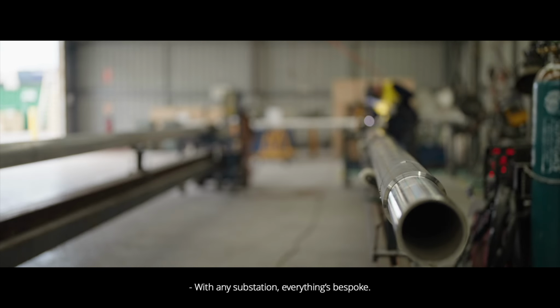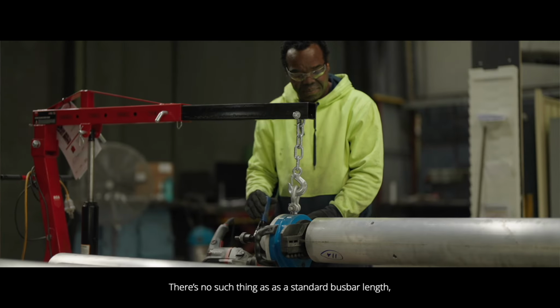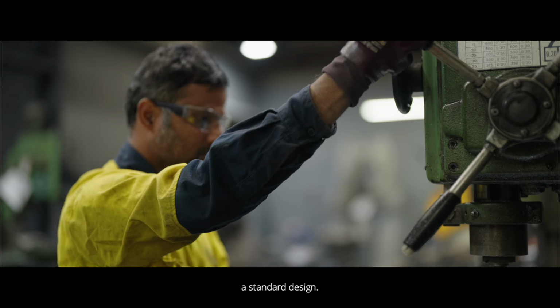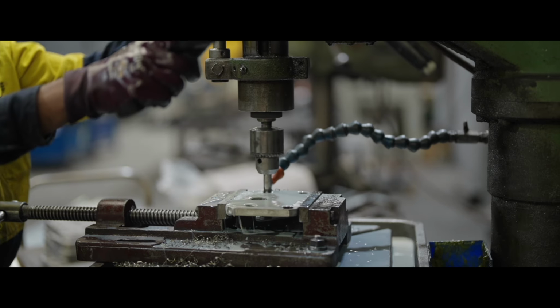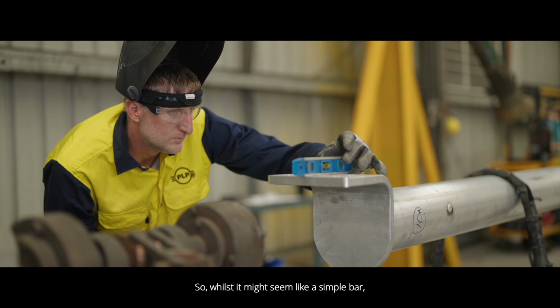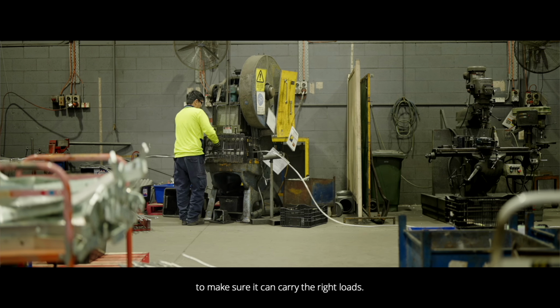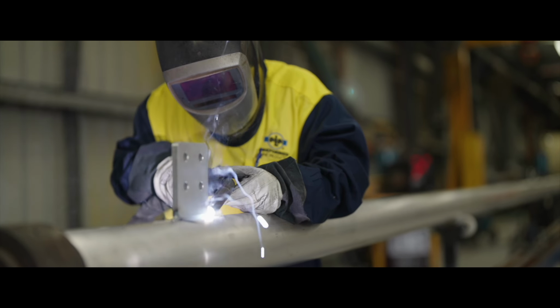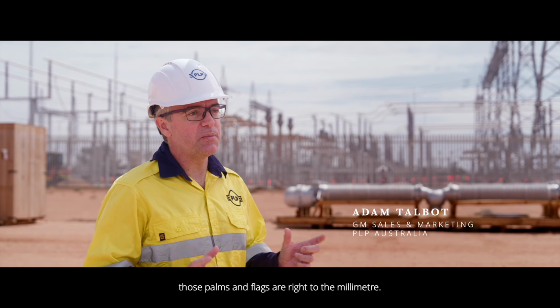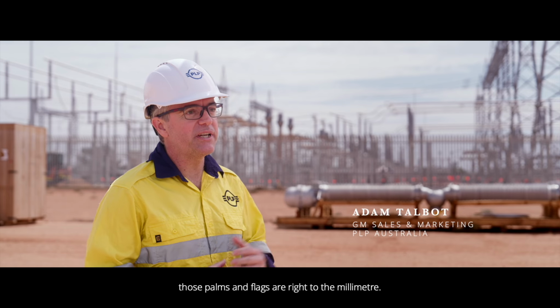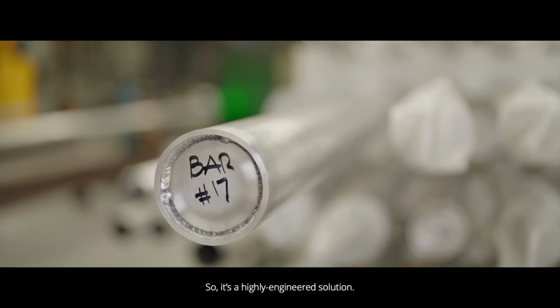With any substation, everything's bespoke. There's no such thing as a standard bus bar length or a standard design. So whilst it might seem like a simple bar, there's been a lot of engineering gone into it to make sure it can carry the right loads. Where anything's welded onto it, those palms and flags are right to the millimetre, so it's a highly engineered solution.